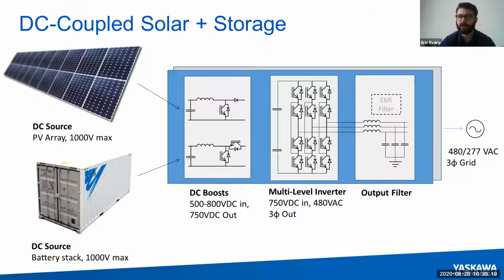We also do some power electronics on the DC side to match the charge and discharge voltages for the batteries -- we have to manage that appropriately, so we have a charge controller specific to the batteries. The PV has its MPPT voltage, and as irradiance changes throughout the day, we vary the voltage on the array to extract maximum power. That voltage the inverter uses will never be the correct voltage for the batteries to charge and discharge, so we need an intermediary to manage that.